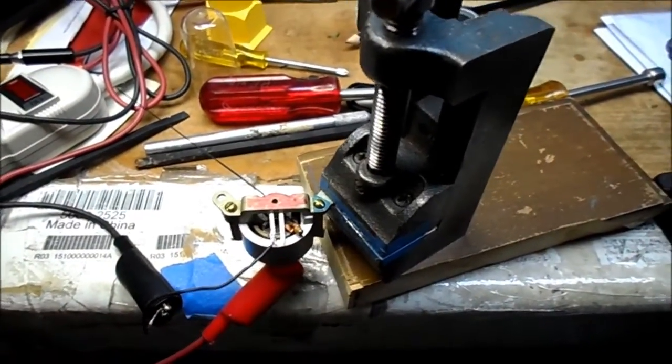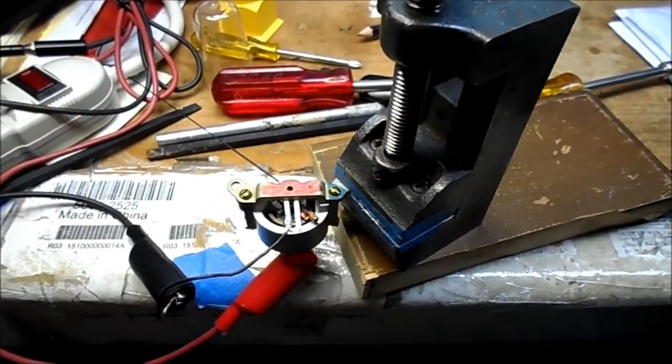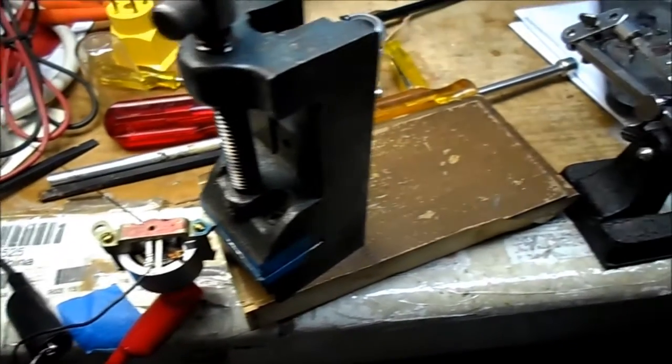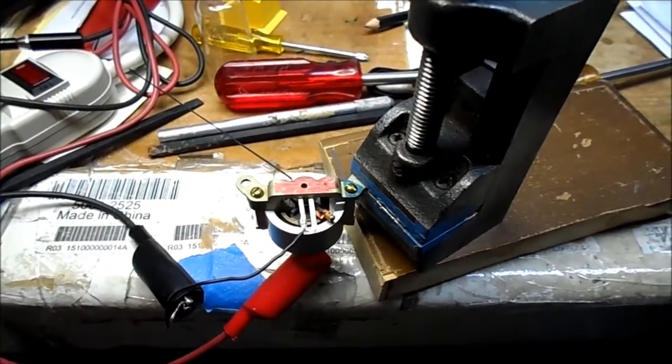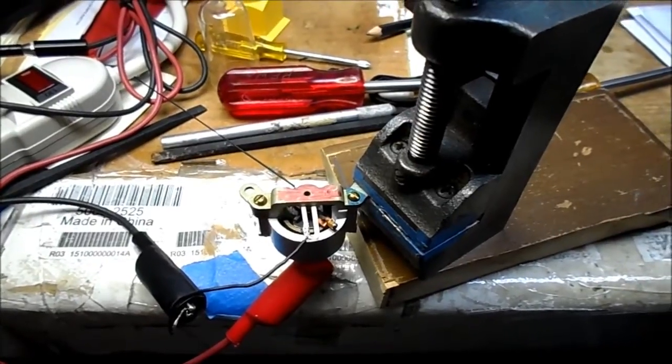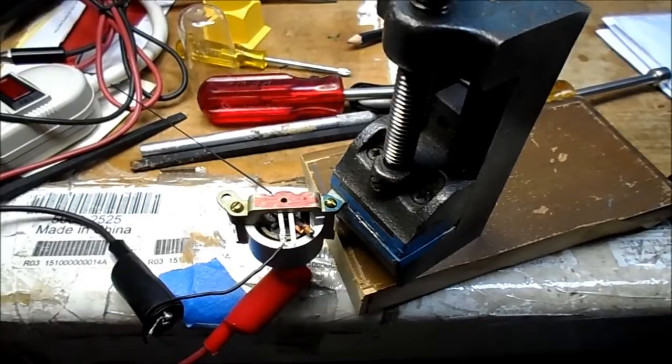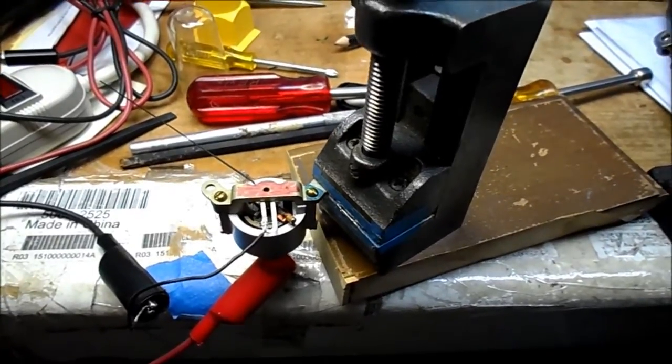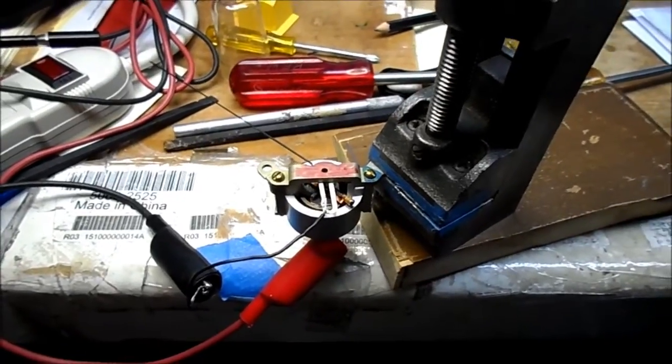It was working fine except the meter was not on zero. Being familiar with meters, I was going to zero it out mechanically. Well, stay away from that with these meters. Someone had already been in here and adjusted the zero. I've seen others painstakingly try to remedy this. This is the Achilles heel of this meter - the meter itself.